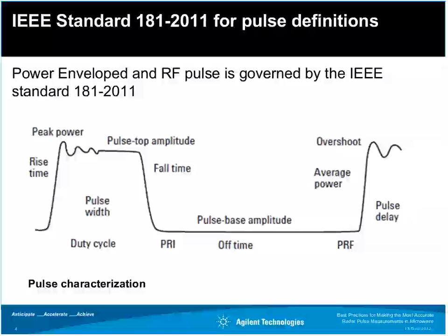A common definition and algorithm are important to ensure that equipment from all manufacturers are returning accurate and consistent results. All Agilent power meters and sensors are referenced to this standard for measurement computation in order to ensure measurement consistency.